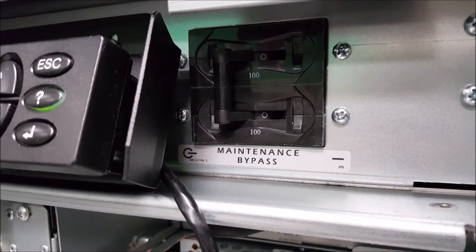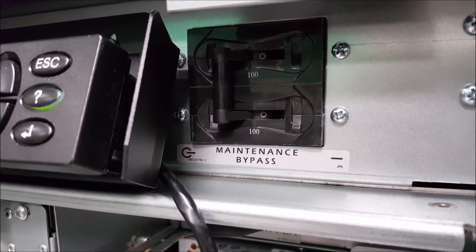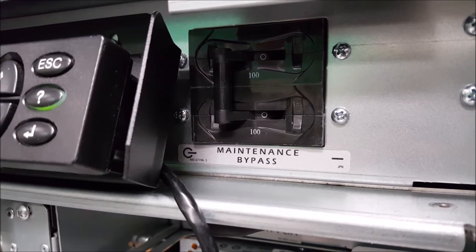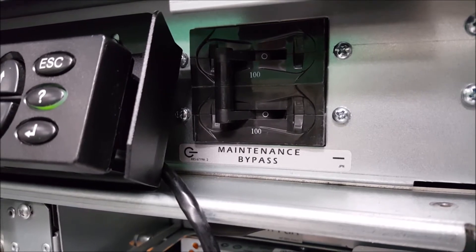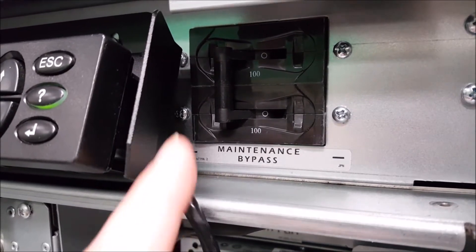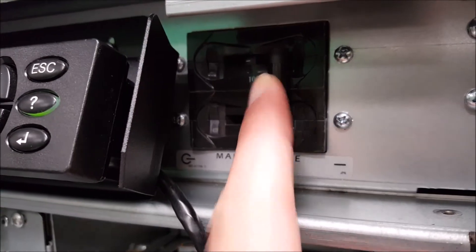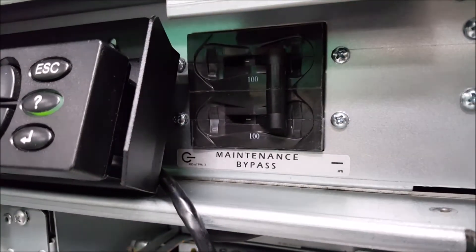Once the UPS is successfully in logical bypass, you'll next want to turn on the maintenance bypass, which is a switch to the right of the display. You'll switch it from the left position, which is off, to the right position, which is on.